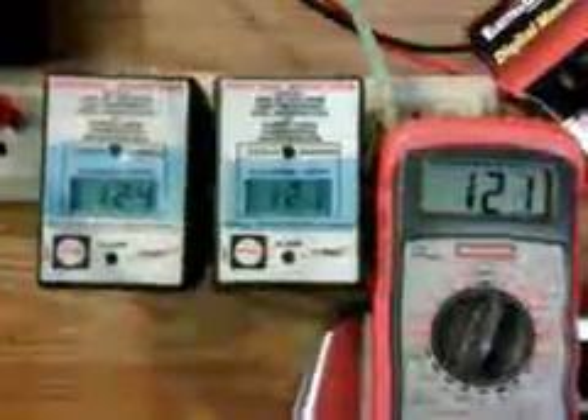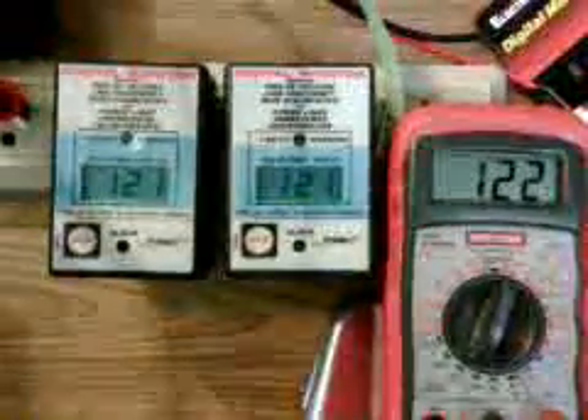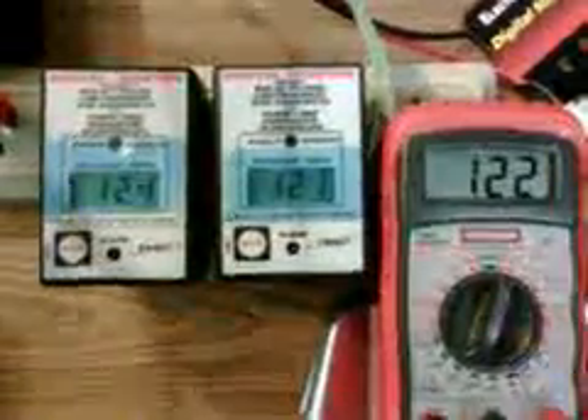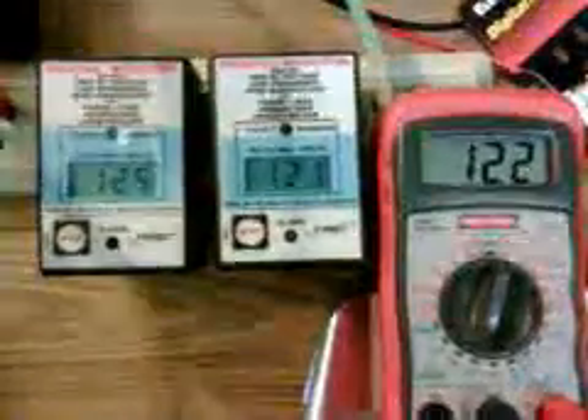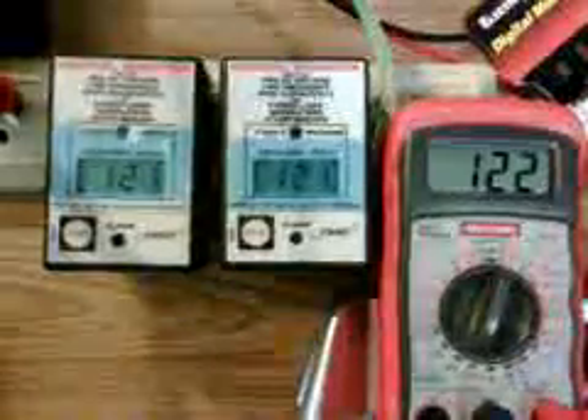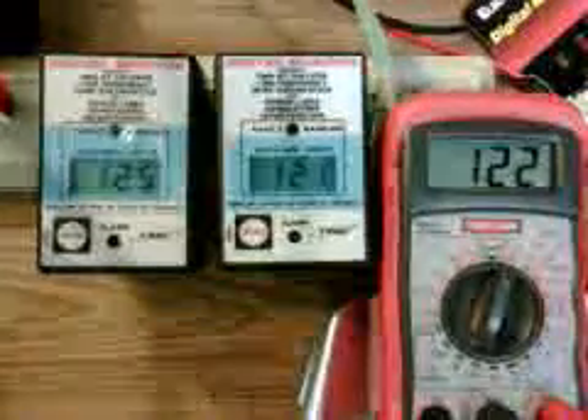Now a little pet peeve I have about these digital voltage monitors too. I've got a device called an auto transformer set up so I can adjust the voltage and purposely trip the alarm. I'm going to take it down to the trip point and you will see that the alarms properly work and go to an alarm. But then there's a complaint — or an observation at least.